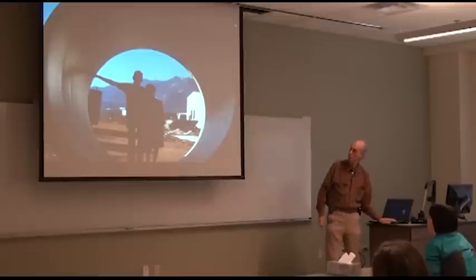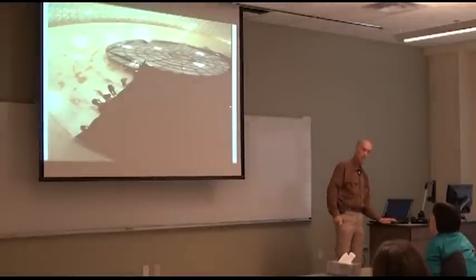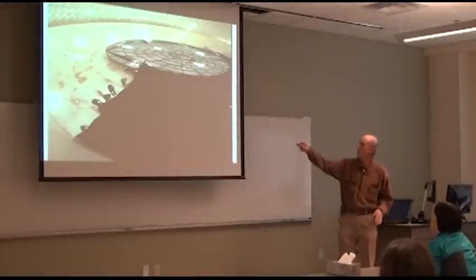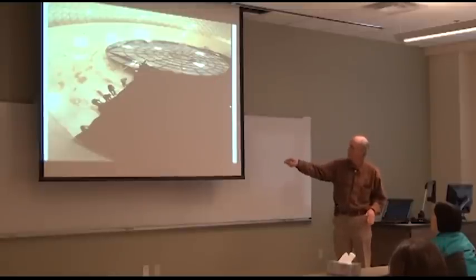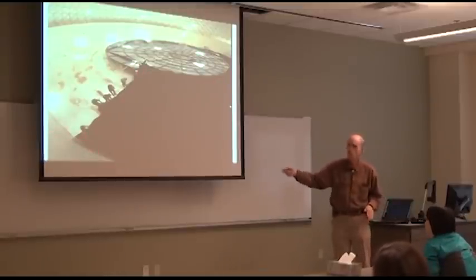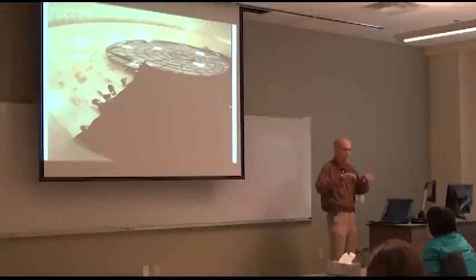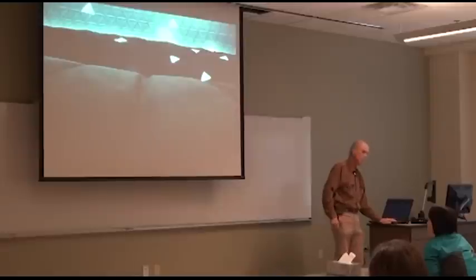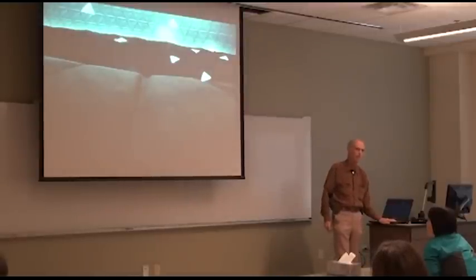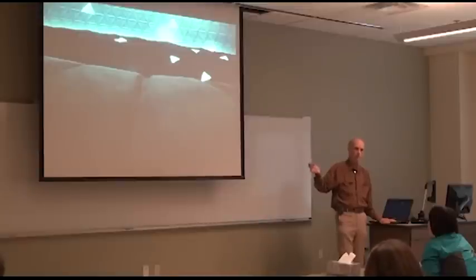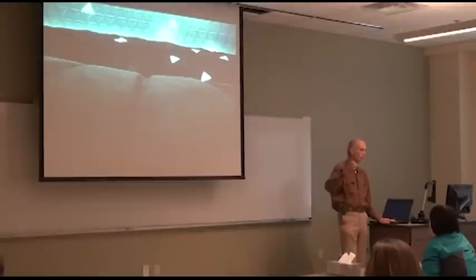Well, that's the tunnel going through. Here's the membrane being placed around the edge of that dish, which connects the edge of the tank to the dish to seal. It's sort of like a donut, a half of a donut shape. And here it is being inflated for the first time. Those tanks were 158 feet in diameter, the dish is 90 feet in diameter, and the range of motion of the dish up and down to absorb the expansion contraction is about 45 feet.